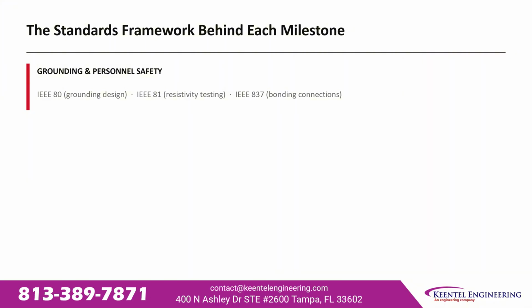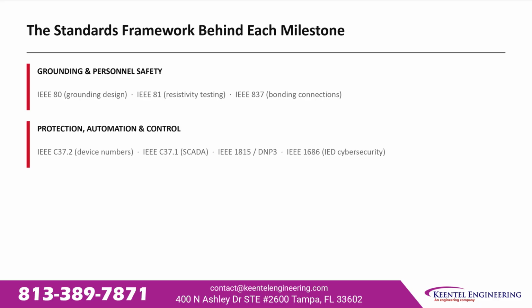IEEE standards and several codes govern substation design across the milestone sequence. For grounding and personnel safety, IEEE 80 for grounding grid design, IEEE 81 for resistivity testing, and IEEE 837 for bonding connections. For protection, automation, and control, IEEE C37.2 for device numbers, IEEE C37.1 for SCADA, IEEE 1815 and DNP3 for communication protocols, and IEEE 1686 for IED cybersecurity.